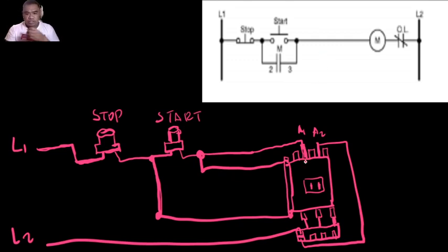In a contactor, the contacts are usually numbered. For the auxiliary contact, the normally open contacts will be numbered ending with 3 and 4, so usually the numbers are 13 and 14. You could interchange the connection because it will not matter, since our control circuit is an AC circuit. So that is how you are going to do the pictorial diagram of your control circuit. This is very useful because you will now have a guide on how to wire your control circuit.